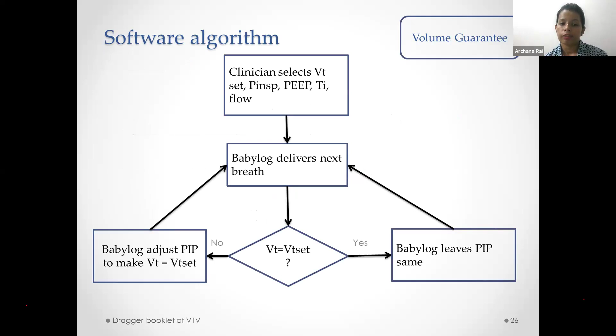So as the ventilator has delivered one breath, it senses how much tidal volume is delivered to the baby. As it was reaching the targeted tidal volume, the ventilator again gives the same PIP to the baby. But at this time, when the ventilator microprocessor senses that this volume has not reached the targeted tidal volume, in the next breath it will increase the working PIP. Then the ventilator senses, okay, this has reached the targeted tidal volume, and the next breath it will deliver the same PIP. This time it has overshot our targeted tidal volume, so in the next breath our working PIP will come down.